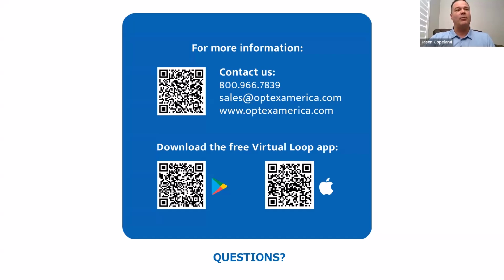Are the outputs normally open and normally closed? Yes, there's an option in the O1. You could push a button to change the state of the relay to either normally open or normally closed. On the O2, this version, you're going to wire it in. It's going to have options for both on the wiring terminal. So you're going to wire it in either normally open or normally closed, whatever you use it for.